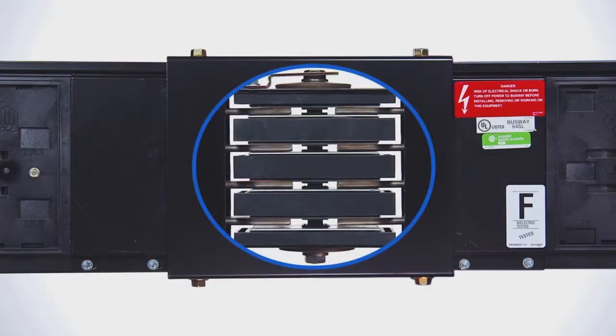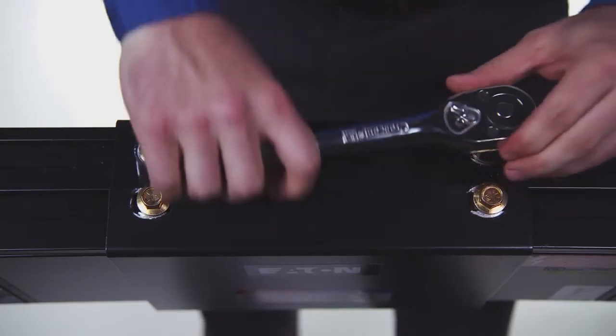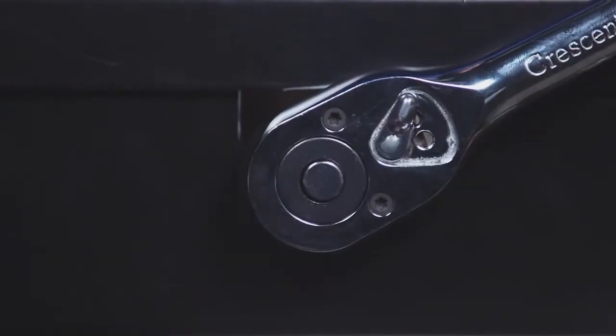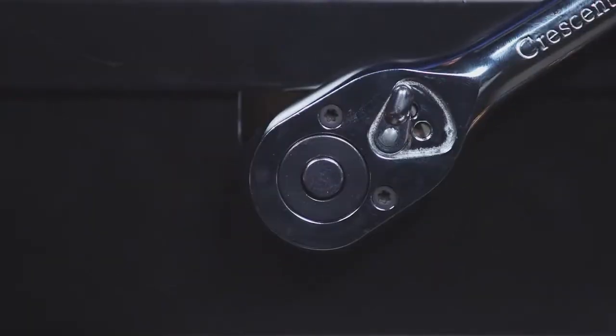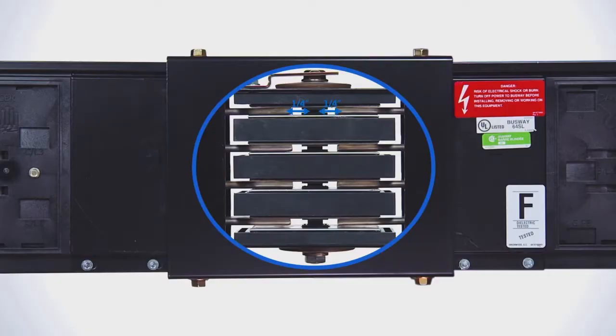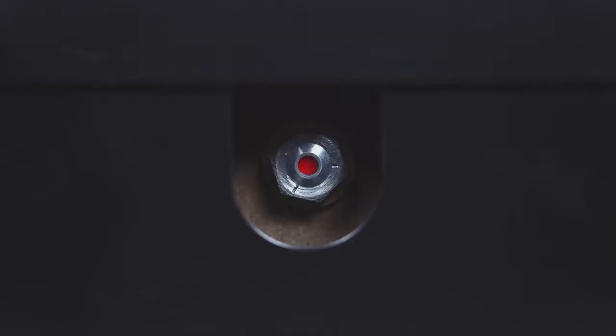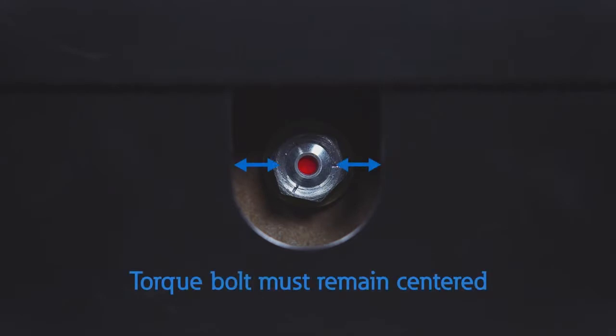Power bridge joints can be adjusted a 1/4 inch in either direction. First, loosen the joint cover bolts and torque bolt. Next, adjust the pieces in or out as required. The maximum distance between bus housings is 7 inches. The minimum is 6 1/2 inches. Remember that the torque bolt must remain centered between the busway housings in order to have proper access for tightening and maintenance.